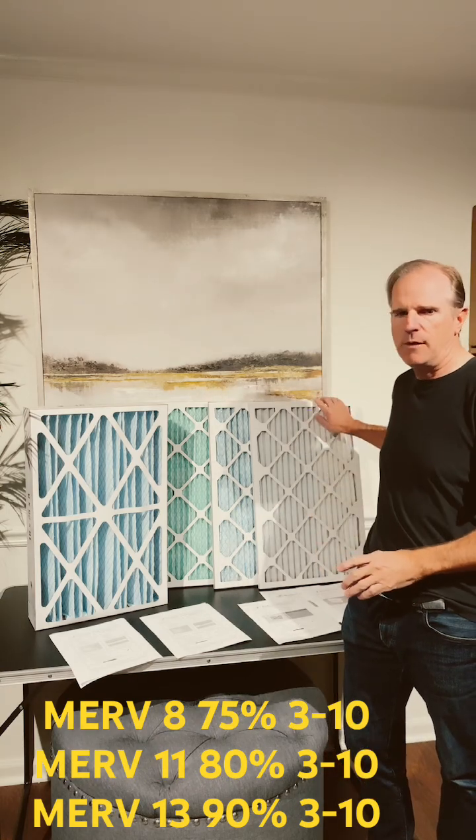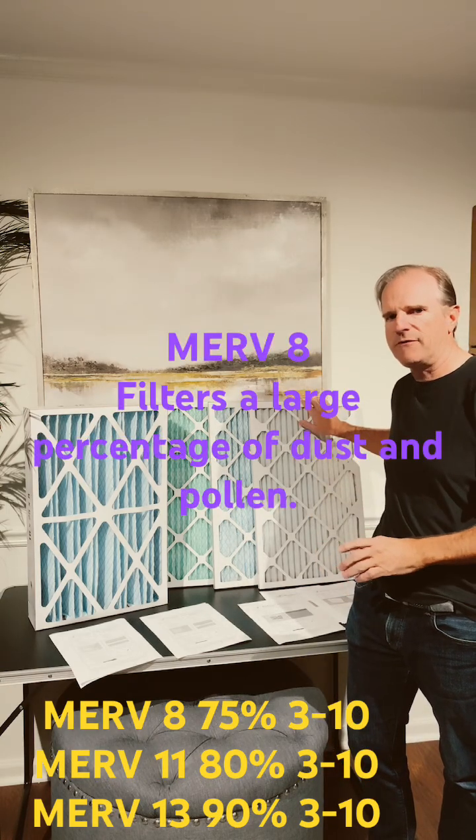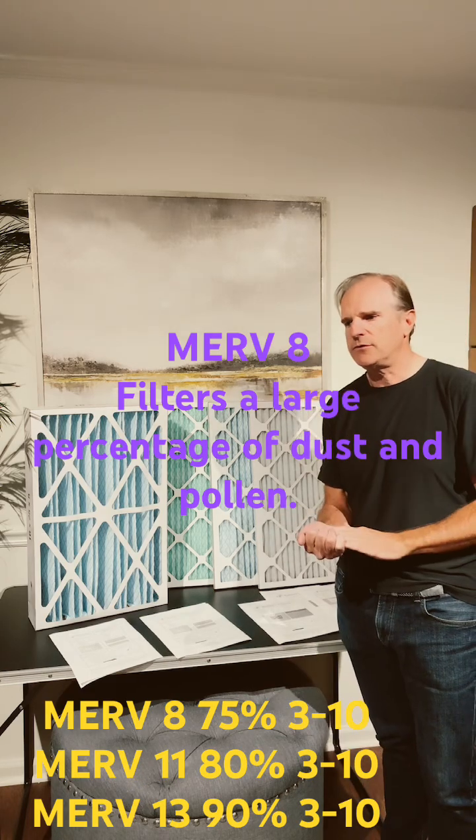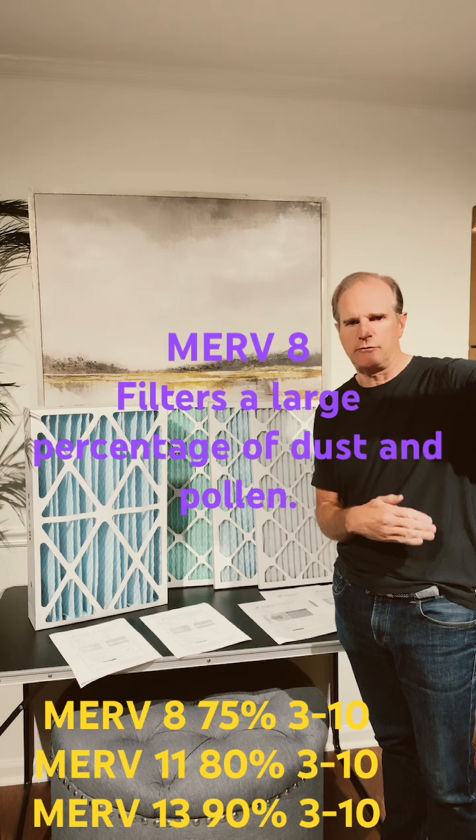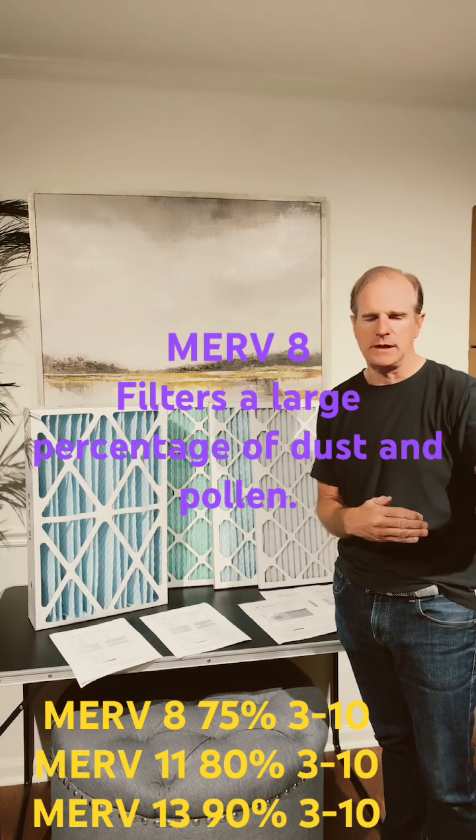A good level of basic air protection would be MERV 8, and that's this white filter here. That's going to filter out 75% of particles from 3 to 10 microns — those are the larger particles like dust and pollen.